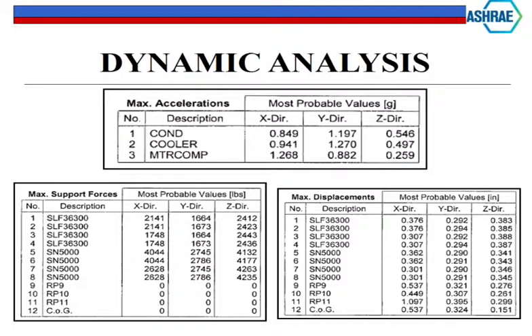So I have to now design a system that can handle that 10 millimeters of movement without shearing off. So basically some kind of snubber that has rubber inside that can handle that 10 millimeters of movement is what you want, because otherwise you're going to start shearing bolts off. So you're going to keep designing these until you get to a number that's in this kind of neighborhood. Otherwise you're looking at having very, very thick rubber, and it becomes more expensive to do it, okay?